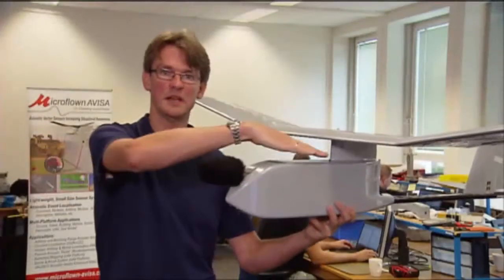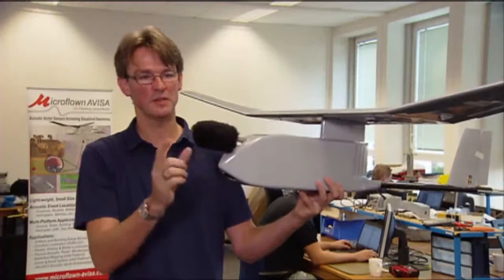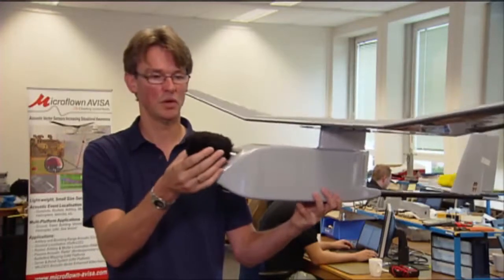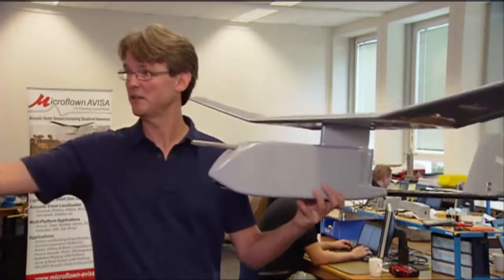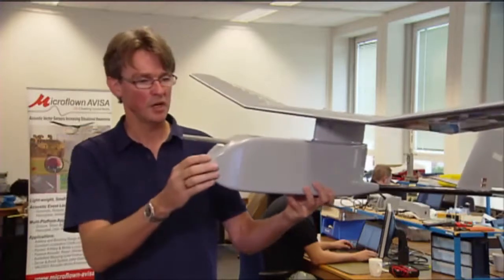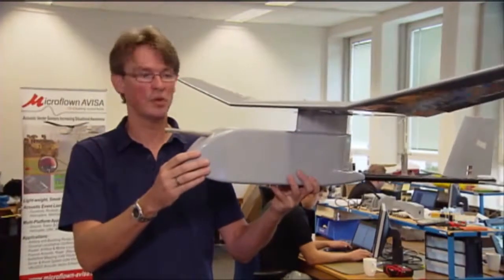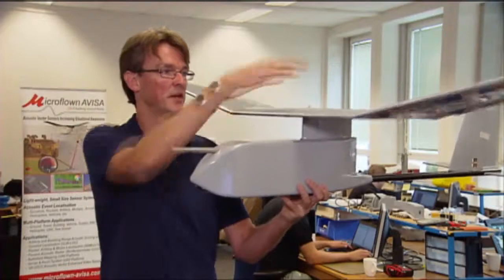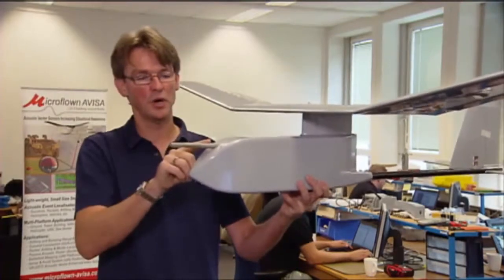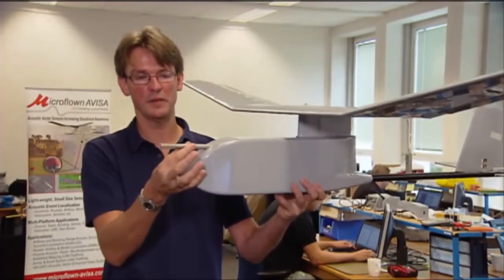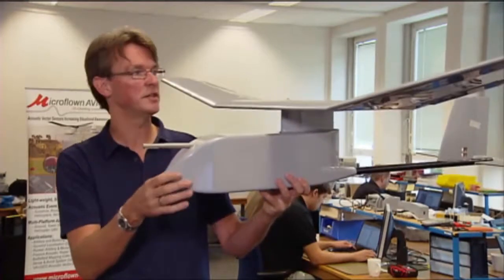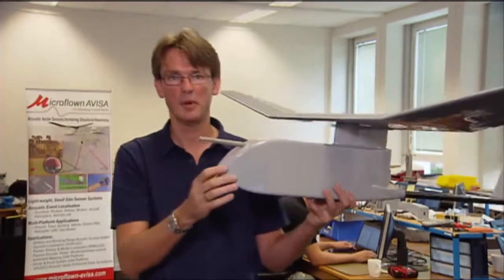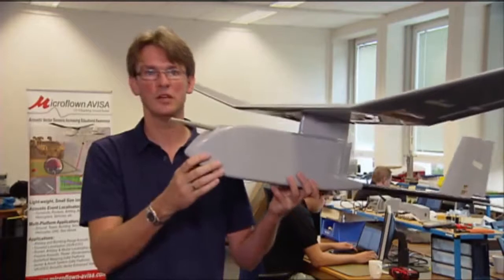If the wind comes in like that, it troubles the measurement, and for that we have a wind cap. Under the wind cap is our Microflown sensor. Another noise source is the platform noise, vibrations which come in from the propeller to the probe, and for that we damp it a little bit. The third noise is the propeller itself, which makes harmonic noise, and that noise we cancel with signal processing.